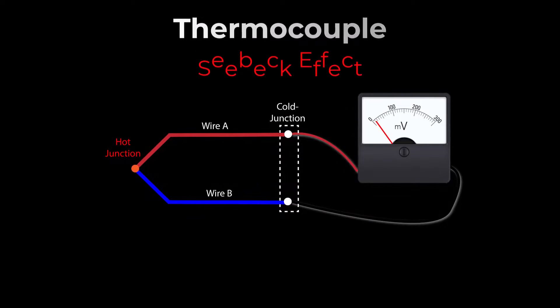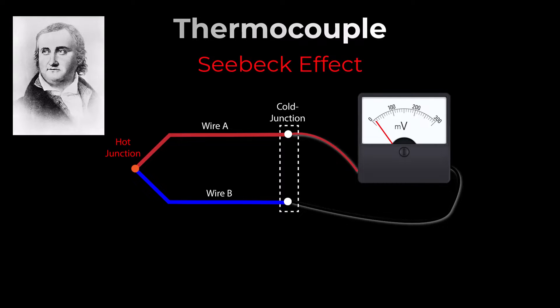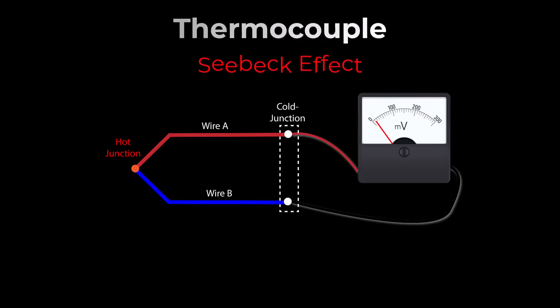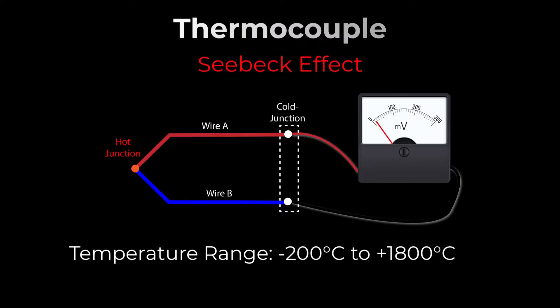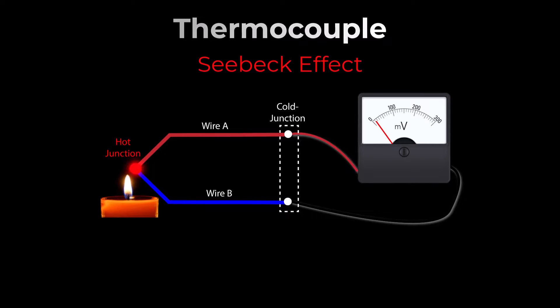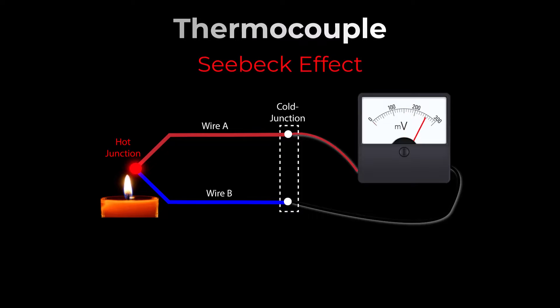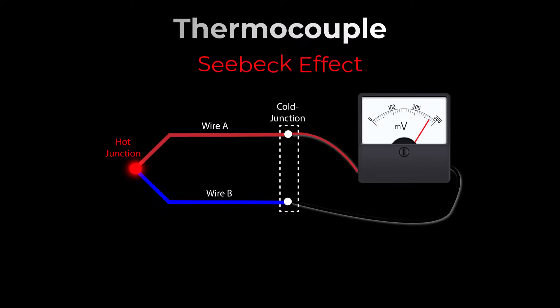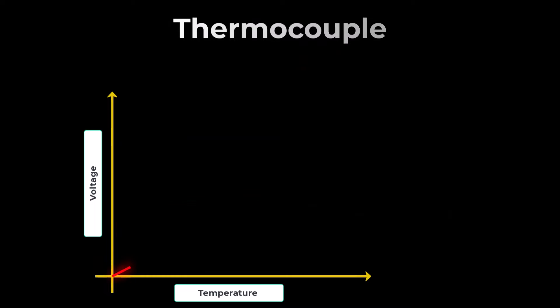It operates on the principle of the Seebeck effect, discovered by Thomas Johann Seebeck in the 19th century. Thermocouples can be used to measure temperatures ranging from minus 200 degrees Celsius to plus 1800 degrees Celsius. The Seebeck effect occurs when two different metals are joined at one end to form a junction, and this junction experiences a temperature difference — it generates a voltage that is directly proportional to that temperature difference.